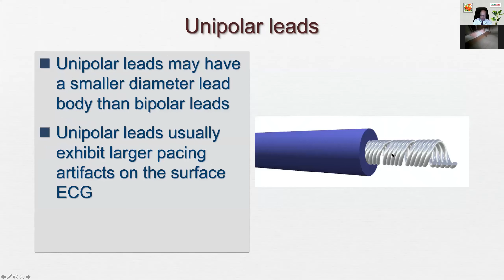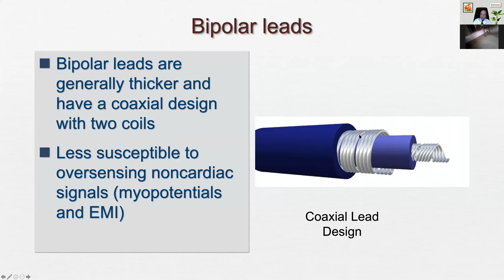So a unipolar lead will have only one conductor, and the bipolar lead has two conductor coils. It's a coaxial design, which means one inside the other. So we have the cathode connected to the inner coil, and we have the anode or ring electrode connected to the outer coil. Now, every pacing circuit has the following characteristics: voltage, current, and impedance.